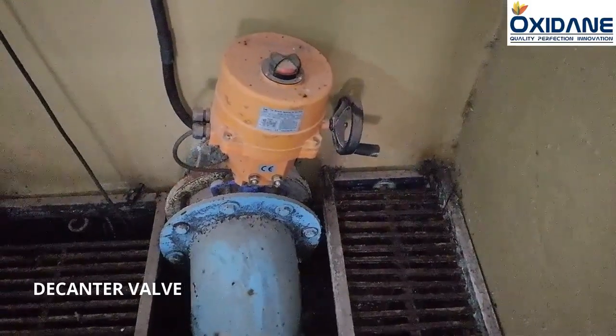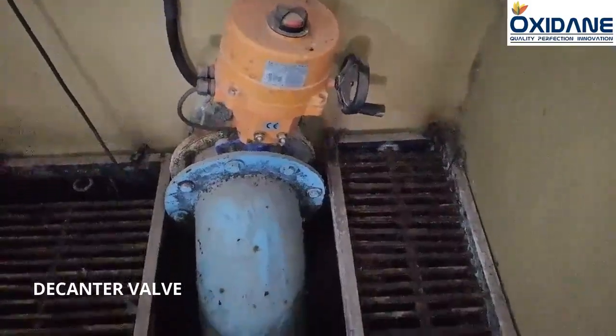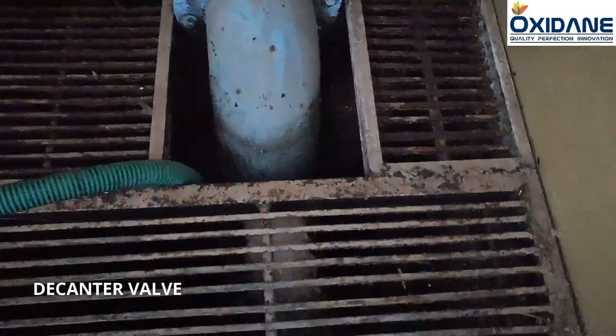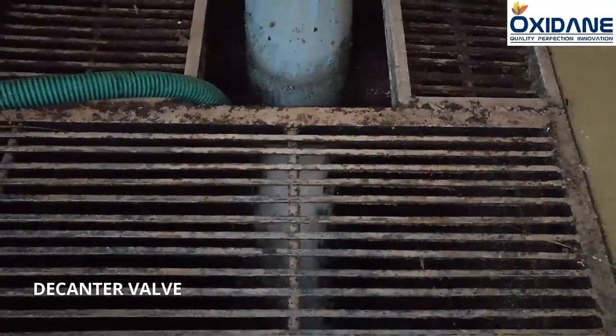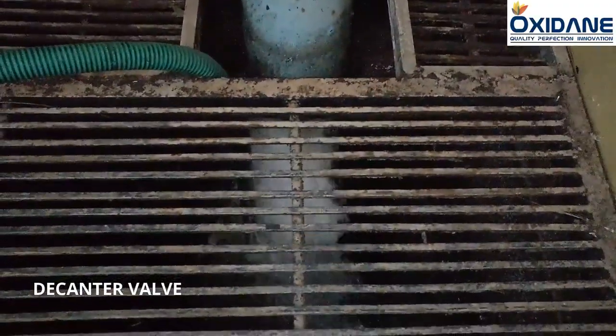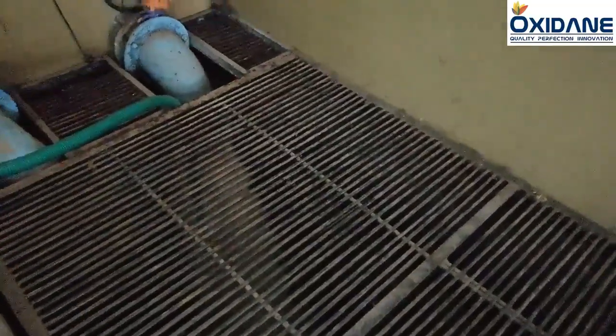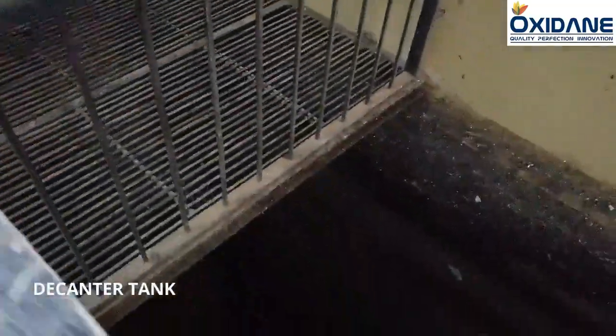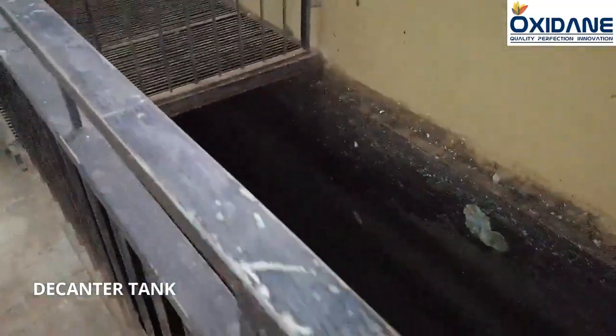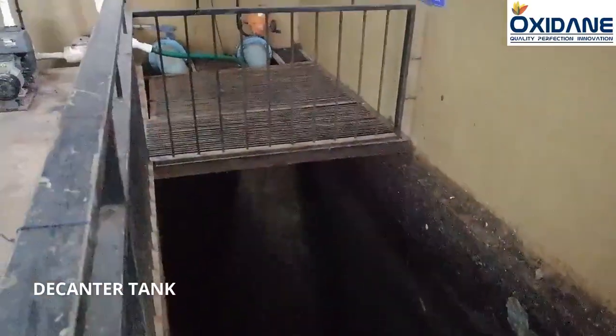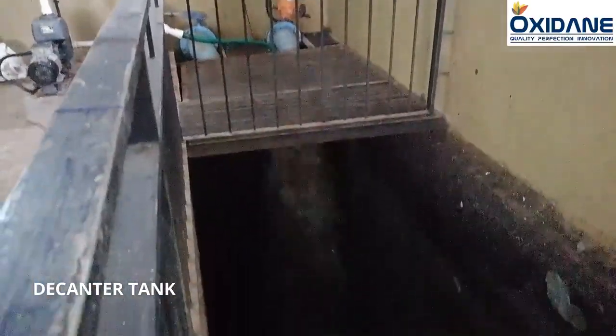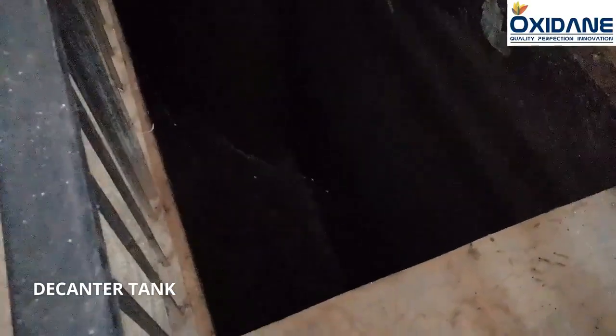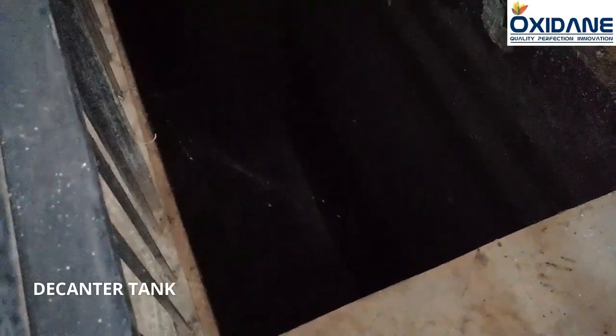Decanter valve. Here, after 1 hour settling in SBR tank, decanter valve will open automatically so that only the fresh water will flow to the decanter tank. Decanter tank's purpose is to hold the fresh water which got separated from solids which comes out from the SBR tank after 1 hour settling through the valve. Once fresh water in the decanter tank reaches a higher level, filter feed pumps will be switched on.